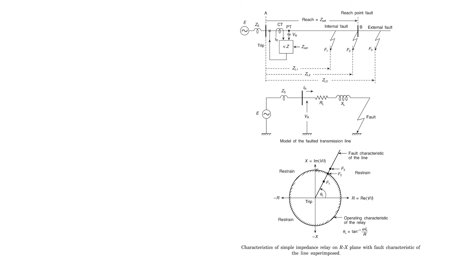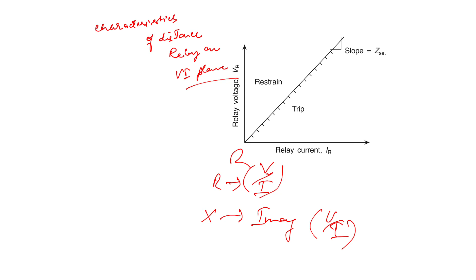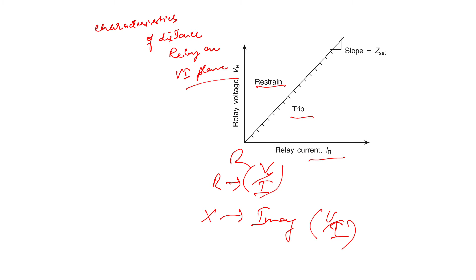So this is shown here in this figure. We have mapped the VI characteristic into the RX plane, and it is a circle, and in this circle we have the trip region and the restraint region. If we consider only the voltage and current axes, this was the trip and this was the restraint region. However, for the analysis we are doing the mapping in the RX plane. Now, in this case let us suppose that we have a system, and in this system we have the fault F2, that is what is desired for Z set.